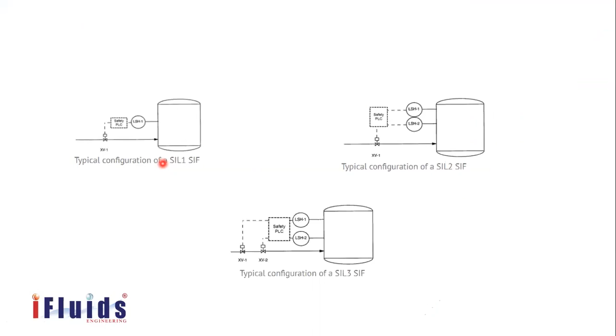Okay. So now you will be able to understand what is SIL 1, SIL 2, and SIL 3. This is one way of doing it. They have 2 out of 3 PTs. You can assume 1 PT failing. For example, if you have 1 PT, 1 logic solver, 1 valve, this PT can fail. If you have 3 PTs, all the 3 PTs failing at the same time is almost impossible. Even 2 PTs failing at the same time is almost impossible, unless it's a real problem in the process. Okay, and you have 2 valves. So even if 1 logic solver operates, it will close both the valves. Even if 1 valve may get stuck, the other valve will help. The other valve will close, so you will be in a safe condition. You are just making sure. This is a safety, so this will not fail.